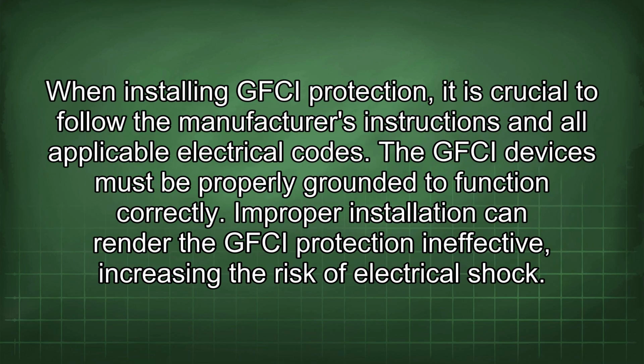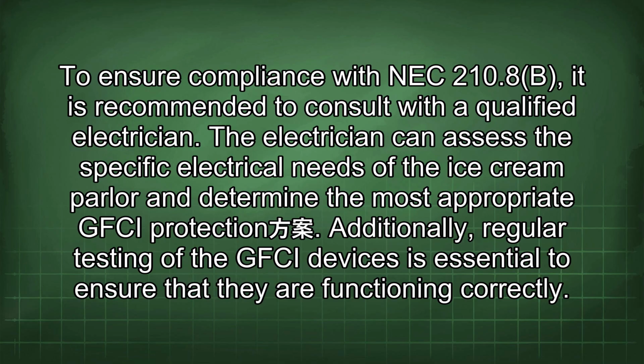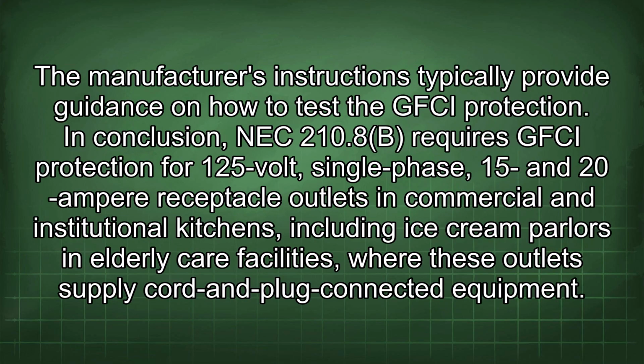When installing GFCI protection, it is crucial to follow the manufacturer's instructions and all applicable electrical codes. The GFCI devices must be properly grounded to function correctly. Improper installation can render the GFCI protection ineffective, increasing the risk of electrical shock. To ensure compliance with NEC 210.8b, it is recommended to consult with a qualified electrician. The electrician can assess the specific electrical needs of the ice cream parlor and determine the most appropriate GFCI protection. Additionally, regular testing of the GFCI devices is essential to ensure that they are functioning correctly. The manufacturer's instructions typically provide guidance on how to test the GFCI protection.